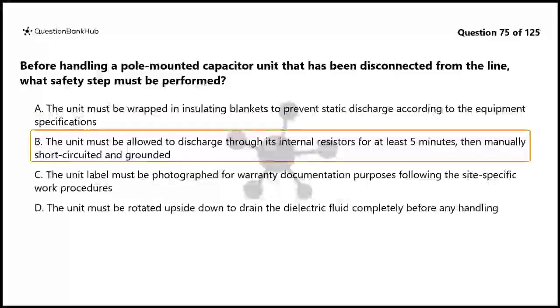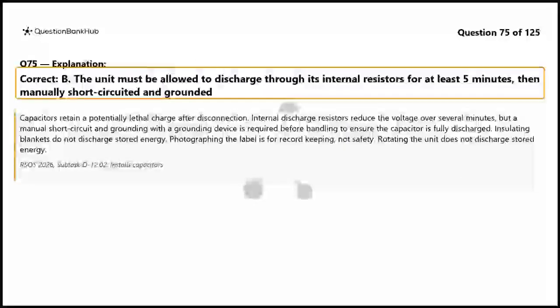The correct answer is B. Capacitors retain a potentially lethal charge after disconnection. Internal discharge resistors reduce the voltage over several minutes, but a manual short circuit and grounding with a grounding device is required before handling to ensure the capacitor is fully discharged. Insulating blankets do not discharge stored energy. Photographing the label is for record keeping, not safety. Rotating the unit does not discharge stored energy.